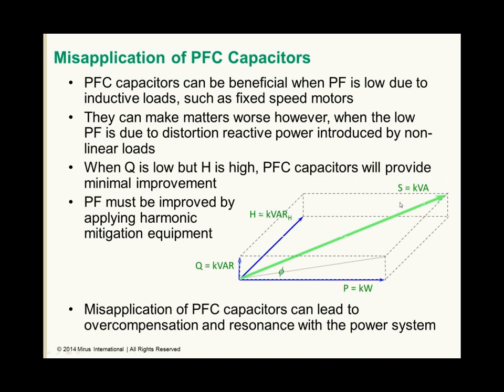The vector sum shows our apparent power configuration. So here, the only way to improve the power factor and reduce the apparent power is to reduce our distortion component. And that requires harmonic mitigation equipment. Misapplication of power factor correction capacitors can lead to overcompensation and resonance with the power system if they're applied when the low power factor is due to distortion.